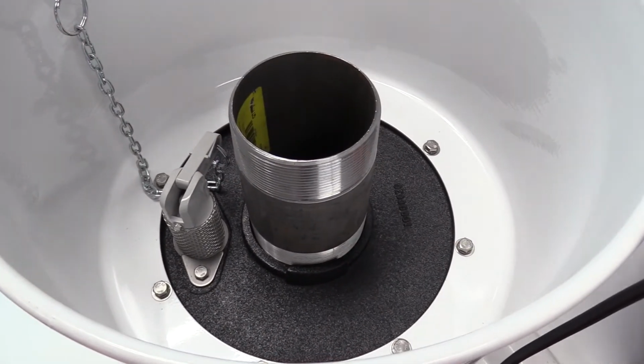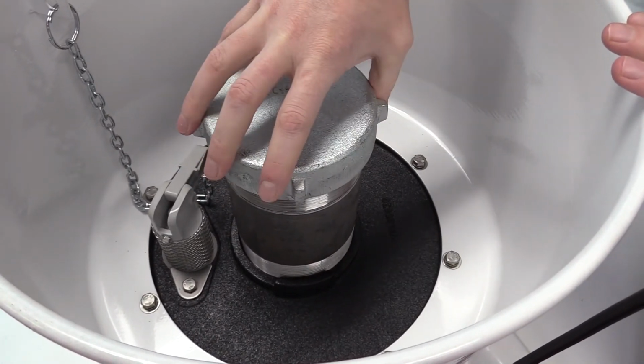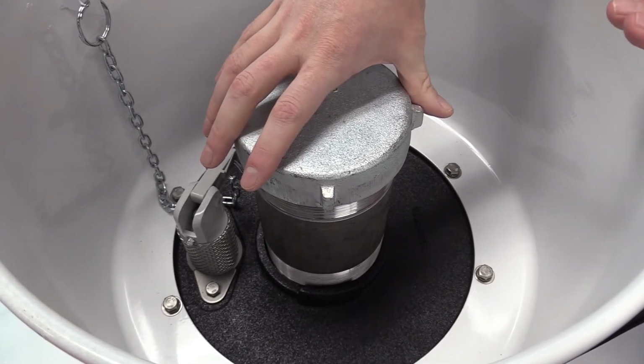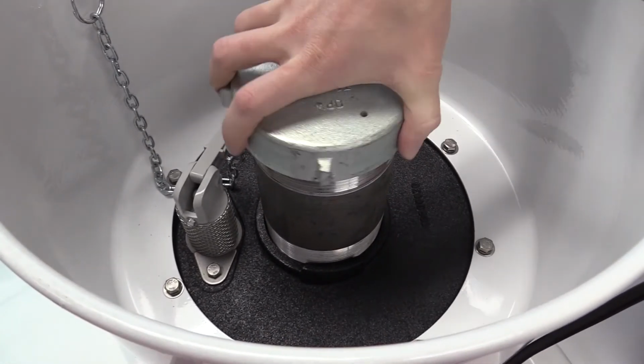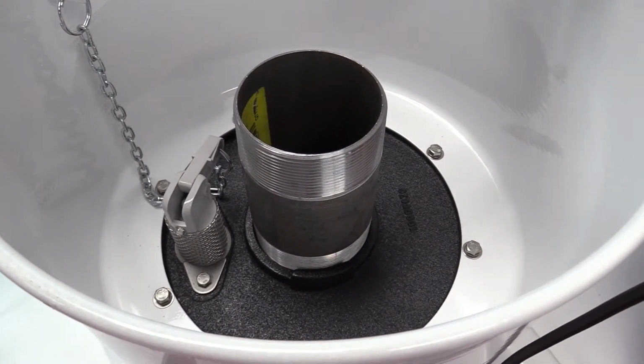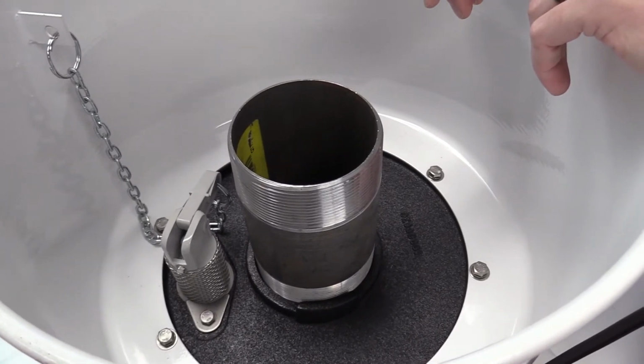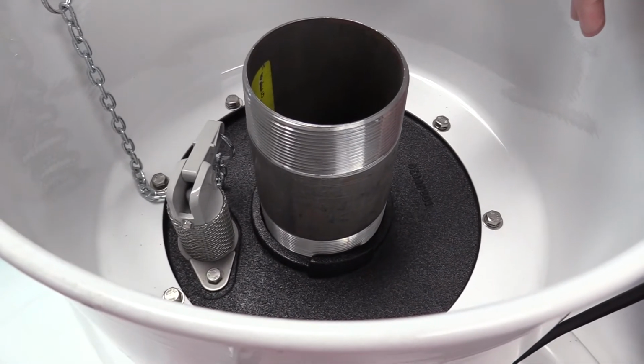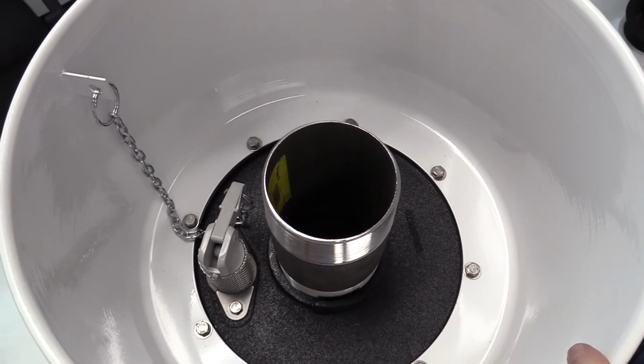And here again we will use our 400 TC to torque this down. Here again this one's going to be 125 to 250, and you'll want to be less torque than the bucket just below it. Once we've got that properly torqued on, now it's time for us to put on our fill adapter, which will be torqued on between 90 and 110 foot-pounds with a strap wrench with a provision for a torque wrench. Should any damage ever come to this 332 series bucket, this is a replaceable part.